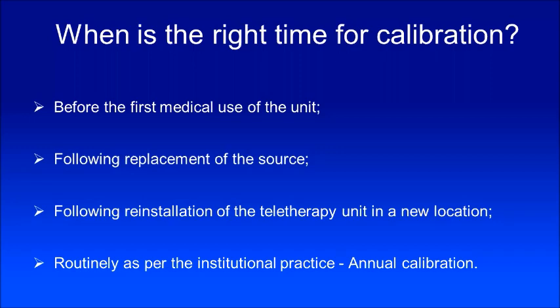When is the right time for calibration or absorbed dose measurement under reference conditions in your LINAC? First, before the first medical use of the unit — if you got a new LINAC or a new cobalt unit, before you go clinical on it, you have to do absorbed dose measurement under reference conditions. Second, following replacement of the source — particularly in cobalt, where you change the source after every five to seven years. Third, following reinstallation of the teletherapy unit in a new location — if you move your cobalt unit or LINAC from one bunker to another, you need to do absorbed dose measurement as per TRS-398.